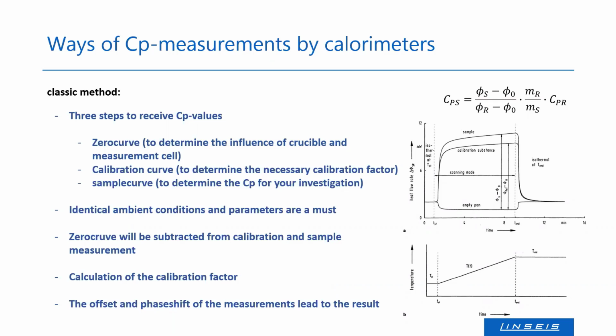So we are checking the rise time here. And above you can see the 3 measurements you need. At the bottom you can see the empty pan, so without anything inside, just the measurement cell and the pan. And a bit higher you can see the calibration substance and the sample. What we already can see here is the heat capacity is higher in this case for this specific sample with this amount. So with this mass it is higher than the calibration substance.